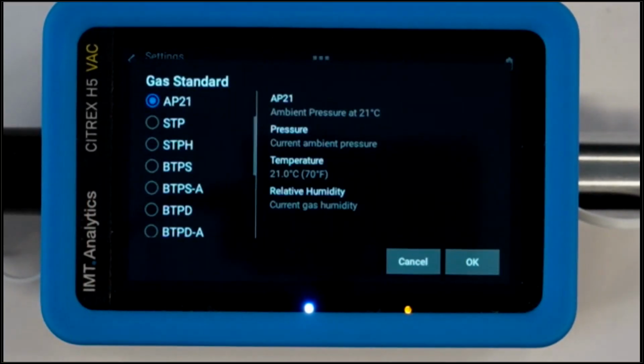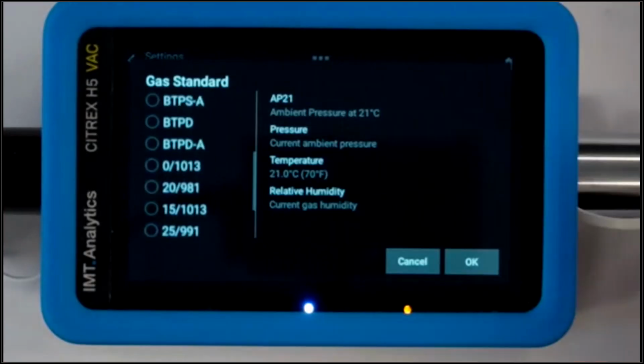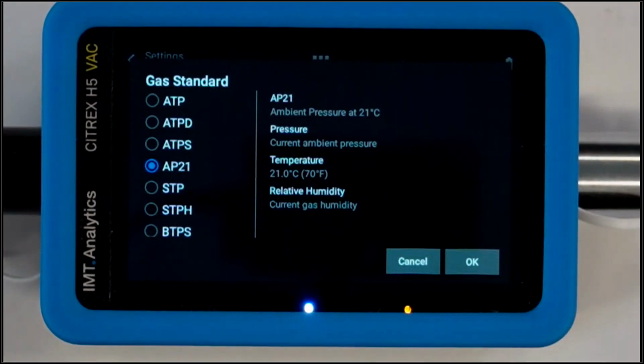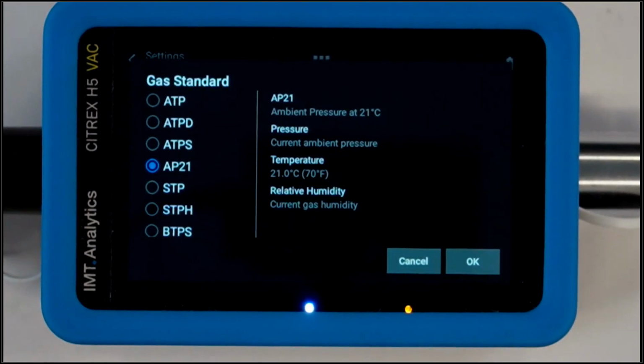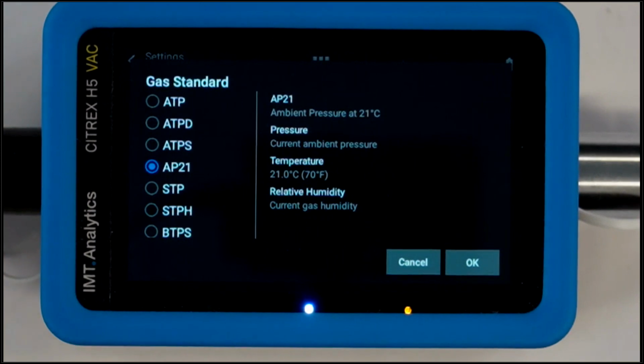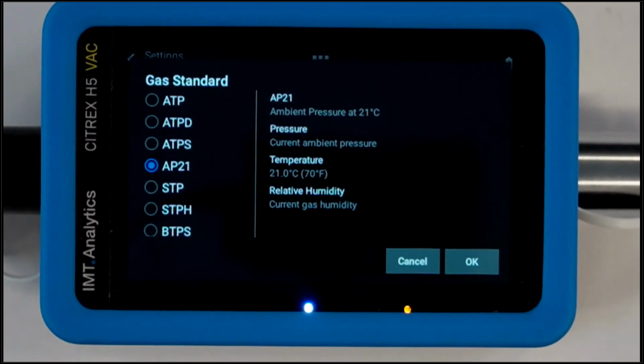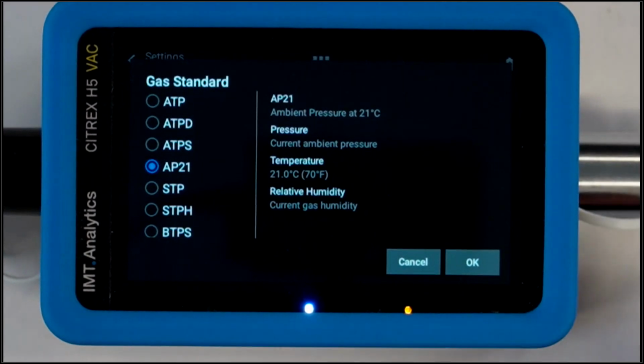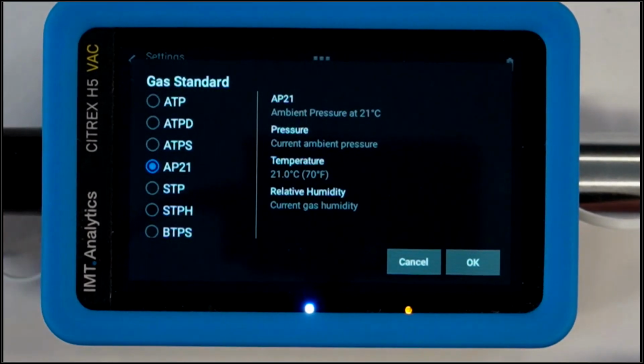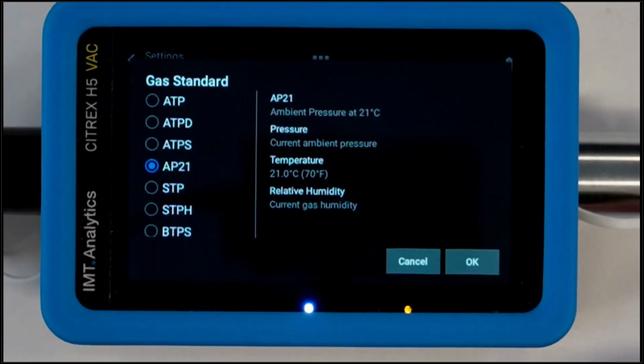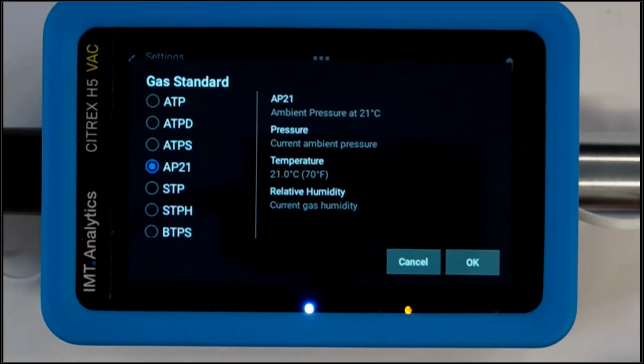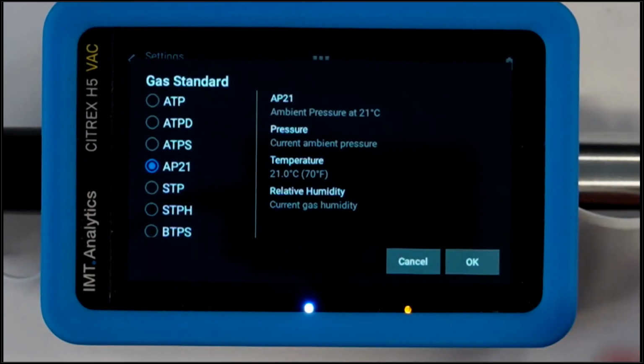So we go to our settings menu, select measurement, select gas standard, and you'll see that we have 17 different gas standards available. Now, most ventilators will either be ATP, STP, or BTPS. In the case of the ventilator we're using here, Bella Vista, it's AP21. And this gas standard has to match. You want to make sure that you're comparing apples to apples, that our device is set for the same gas standard that the manufacturer has set the ventilator to. So you may have to go to the ventilator documentation to find out, because it's not always apparent. But once you know, set the gas standard, move on to the gas type.